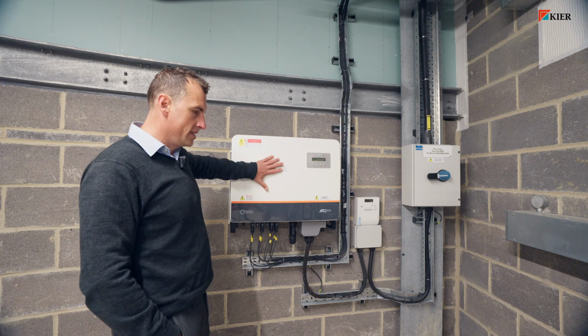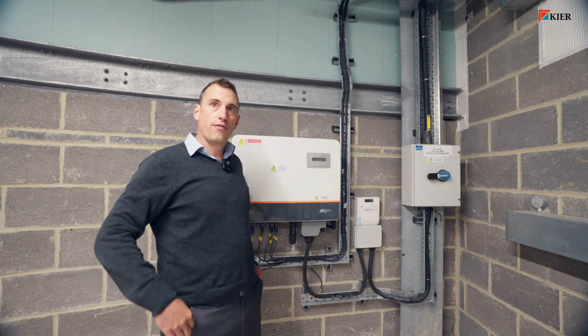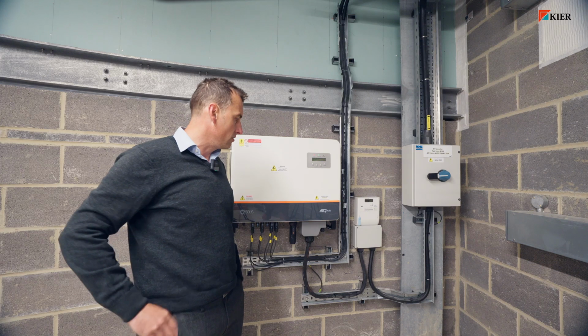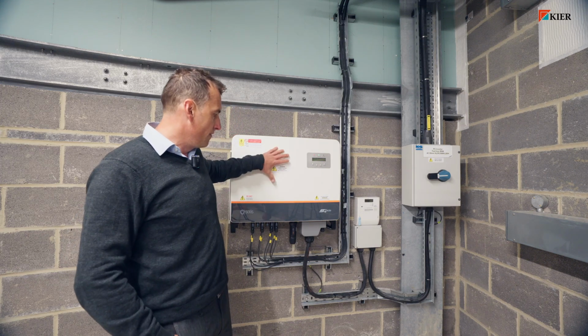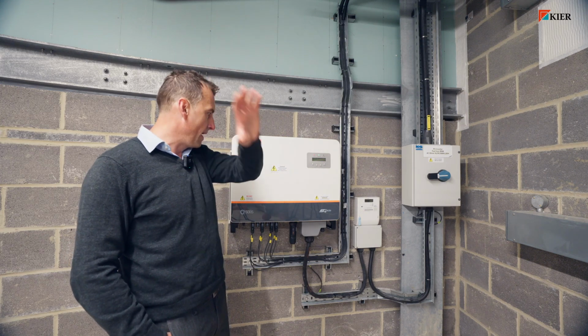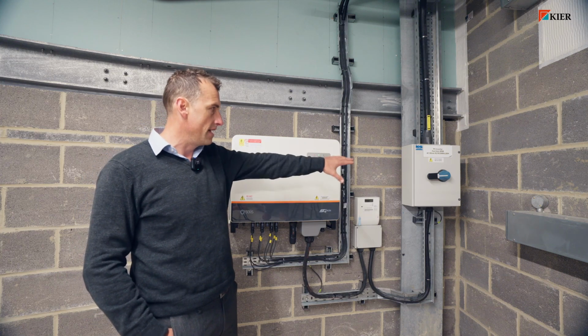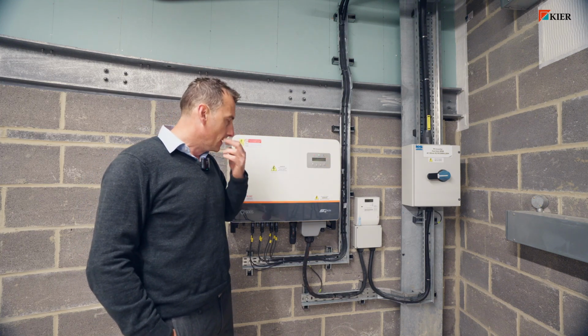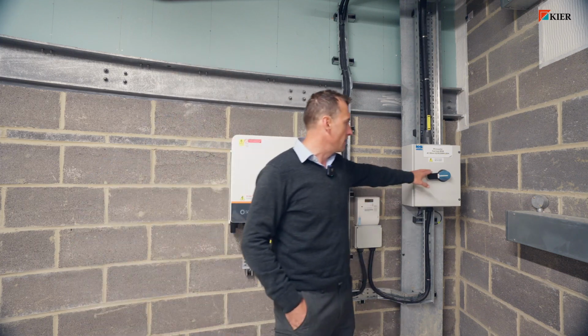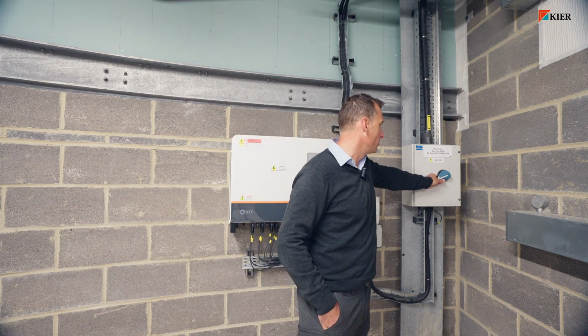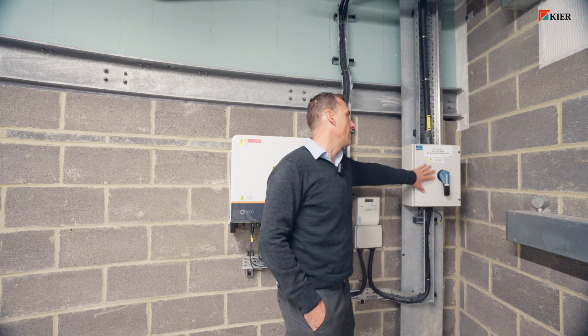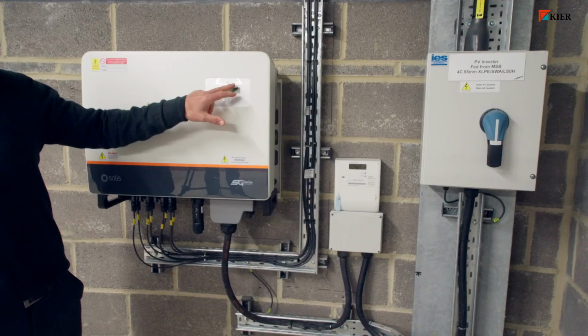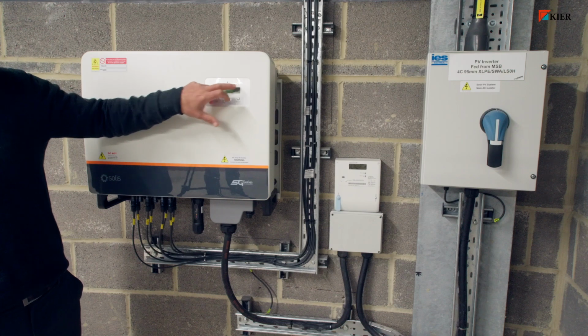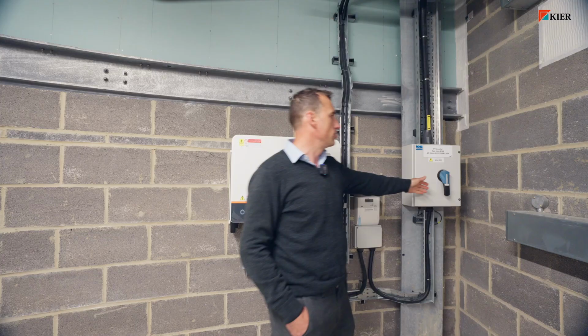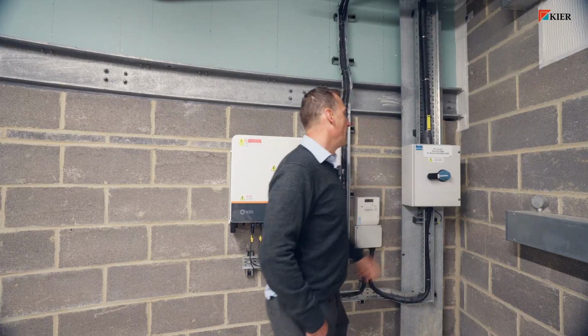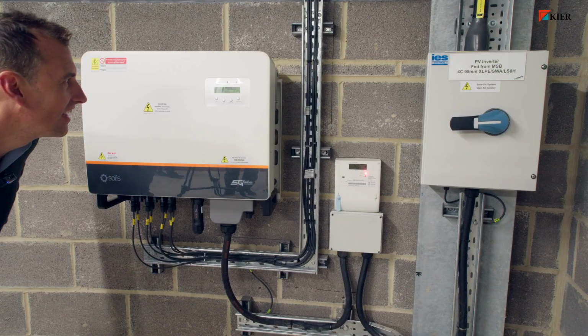This is your PV inverter, which is supplied from all the panels located out on the roof area. So they feed in from the panels into this unit, from this unit via that switch, and then obviously back onto the grid. So in order to isolate this, you'll merely just come across and turn this from on to off, and that will isolate the inverter. And as you can see, the alarm fault has now appeared. Once you want to re-energize it, you're able to just switch this back on, and there will be a time delay, and this alarm will then clear.